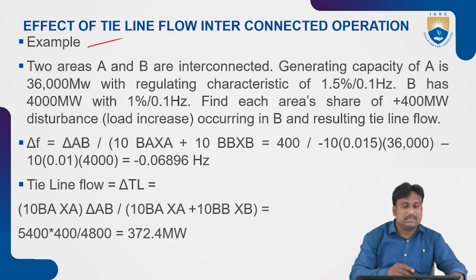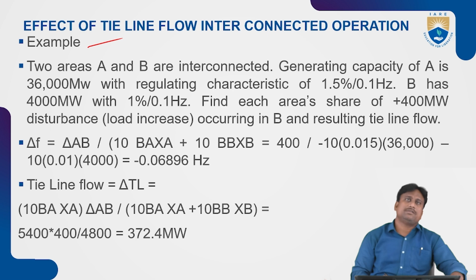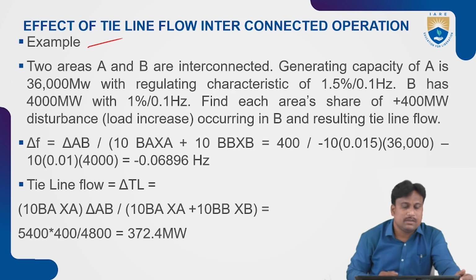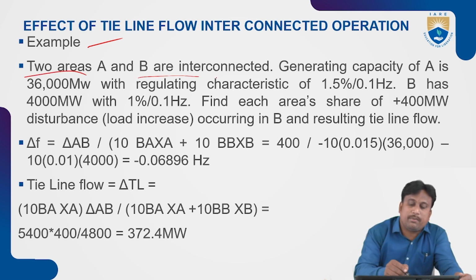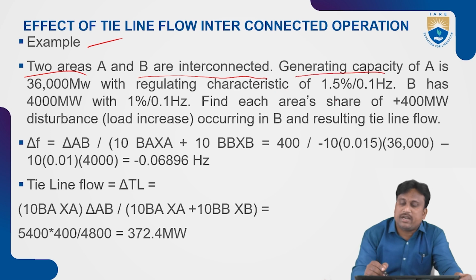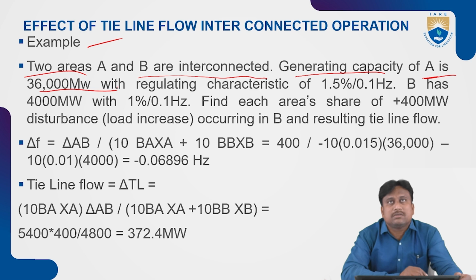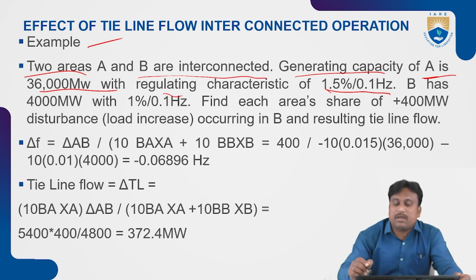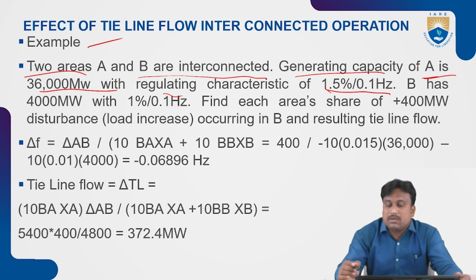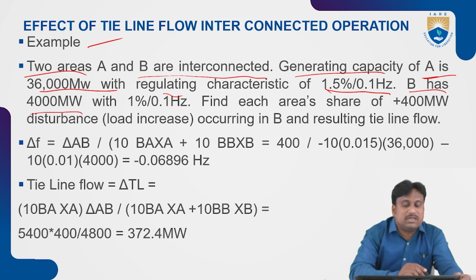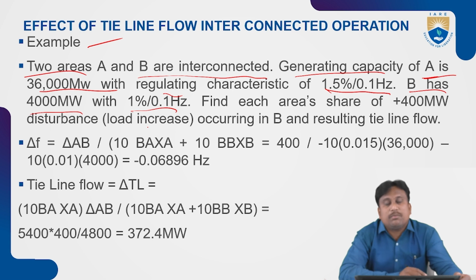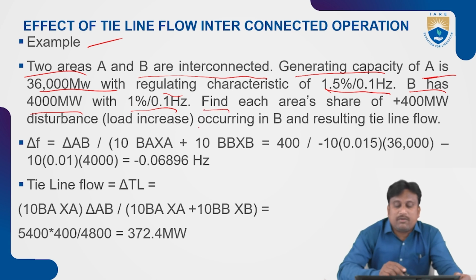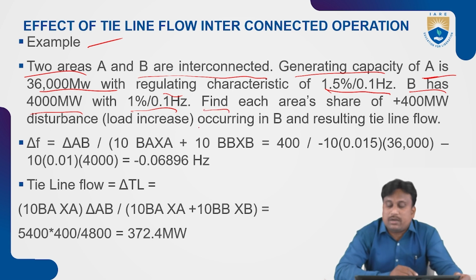So, here is a simple example that resembles how the tie line coefficients are expected with the bias pattern. For example, two areas A and B are interconnected. The generating capacity of A is 36,000 megawatts, with regulating characteristics of 1.5% per 0.1 Hz.